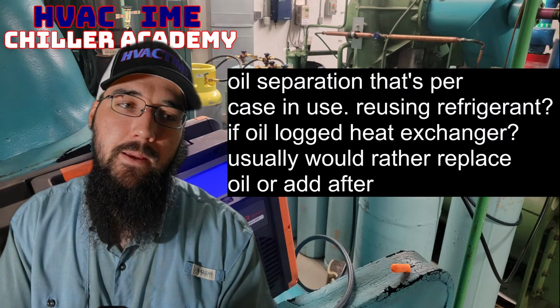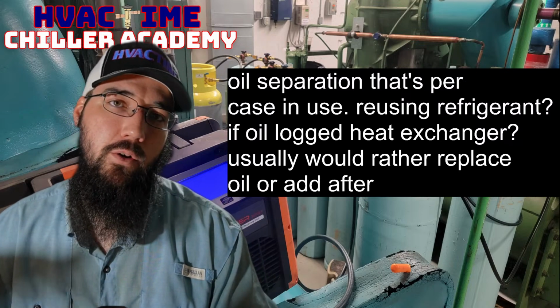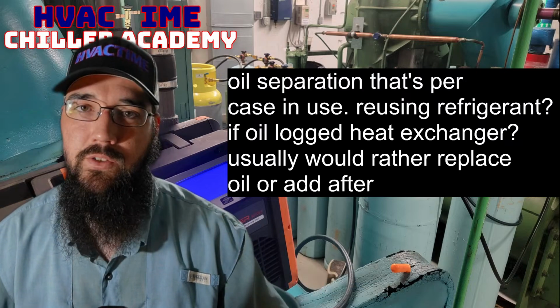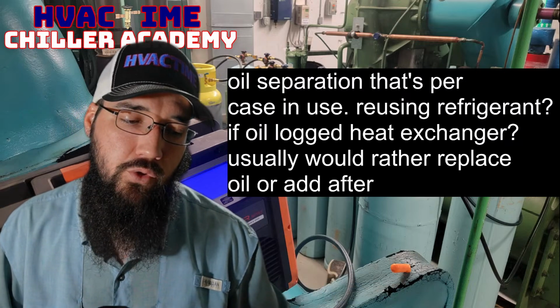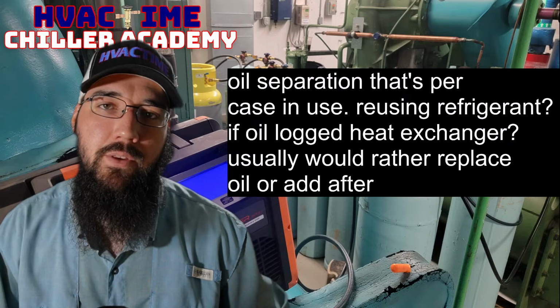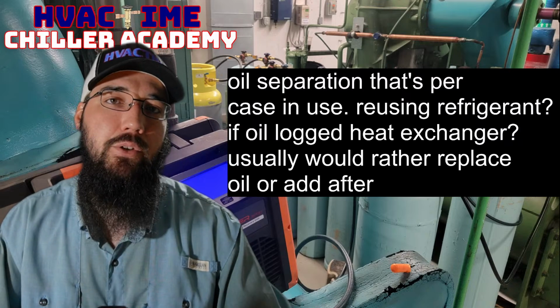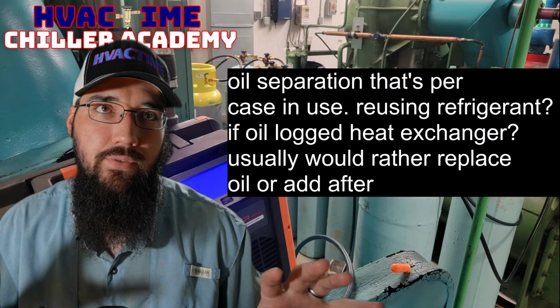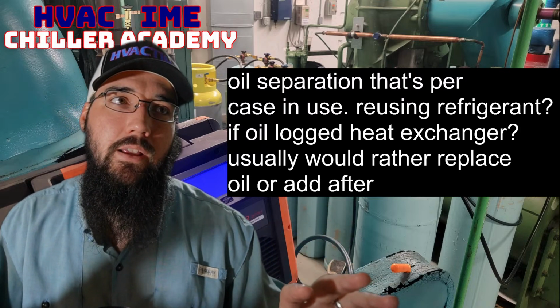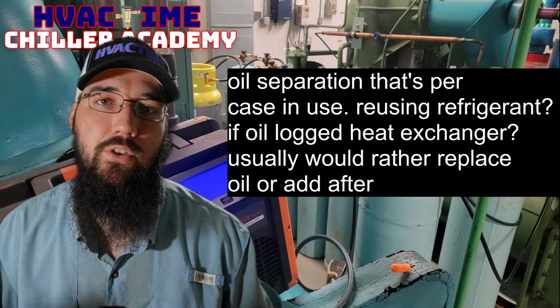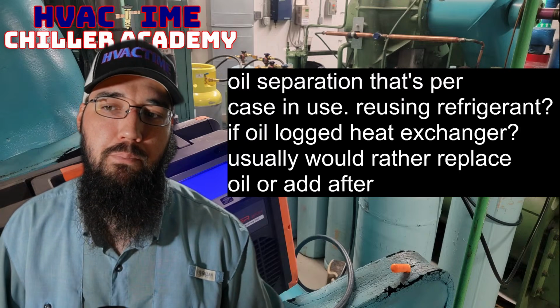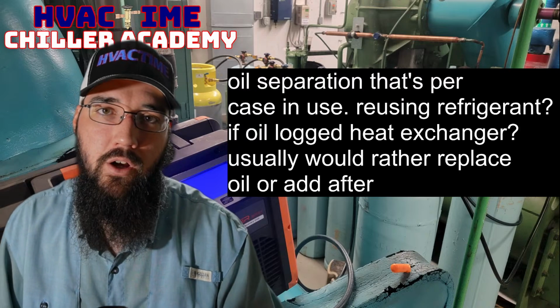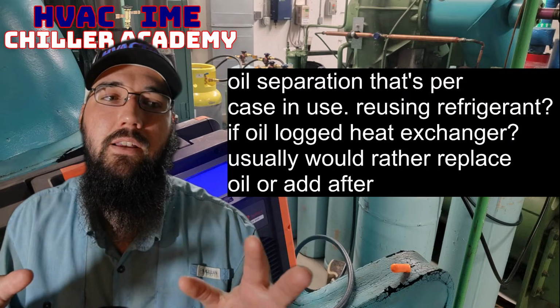You'll get a pretty good amount of that oil back where it needs to be, whether in the sump, the oil separator, whatever the case. On some of these it doesn't take very long, and I would do my best, even if it wasn't completely safe for the machine, but I knew I could make it run for a short time, I would try.